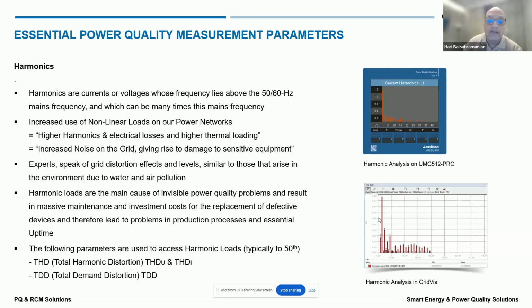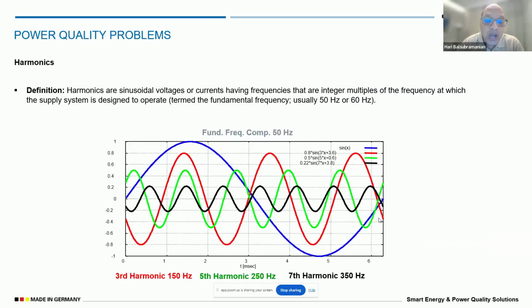I will go back to the slide. Say, for example, you have third, fifth, and seventh harmonics. The blue waveform is the main waveform, but when the third, fifth, and seventh harmonic frequencies are superimposed on the fundamental waveform, then you have a problem, because the fundamental waveform changes according to the noise and the amplitude of the harmonic currents that we have.